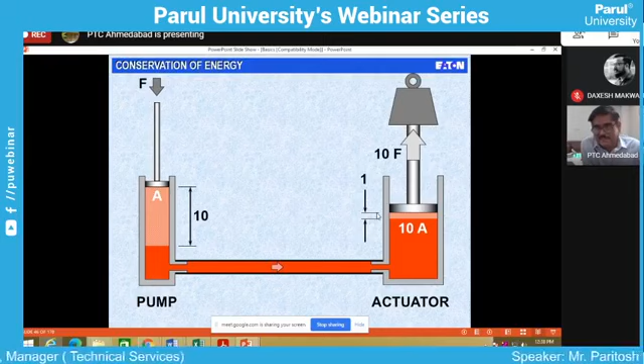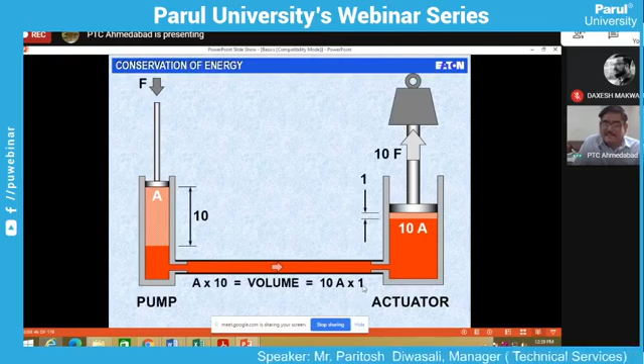Here you have traveled 10 cm down, whereby you are going 1 cm up. The total volume swept by you at the pump side is 10 centimeter square into 10 cm in length, that is 100 cm cube. To sweep a similar volume at the actuator side, the actuator has a piston area of 100 cm square, so if you travel only 1 cm, the total volume swept is 100 cm cube. The area is 10 times, and the distance is 1 cm, which gives the similar volume.